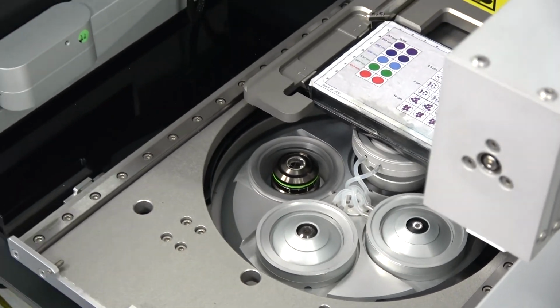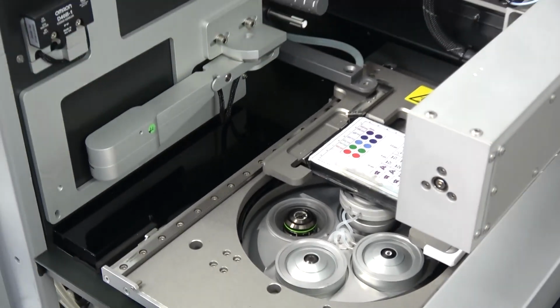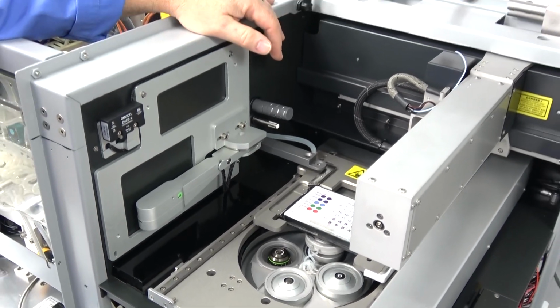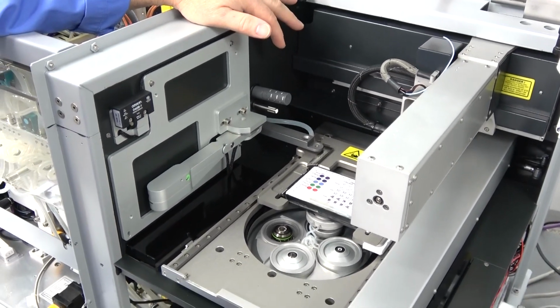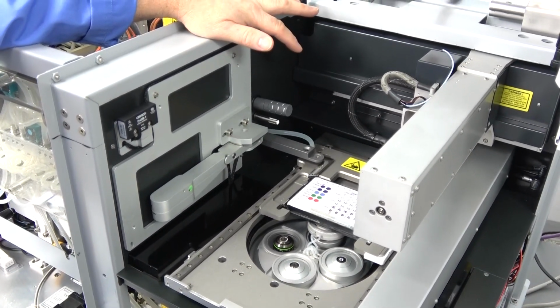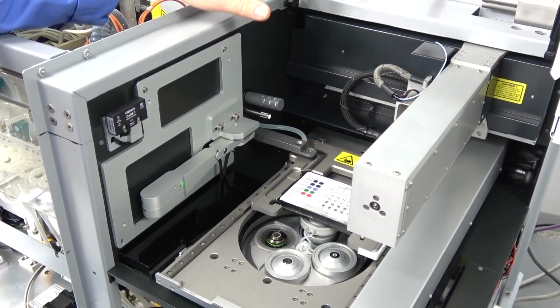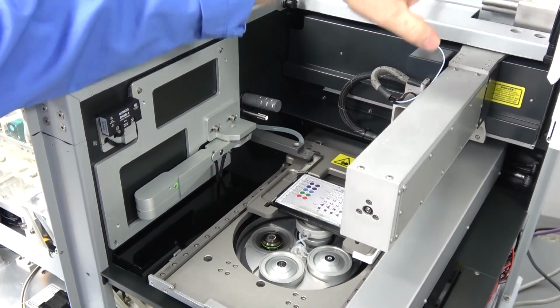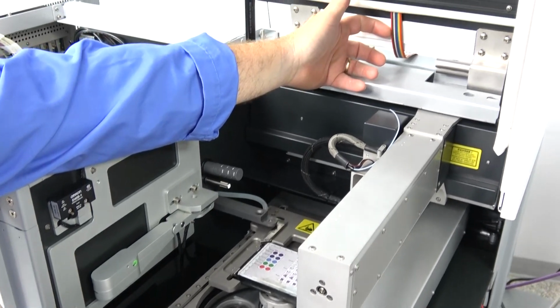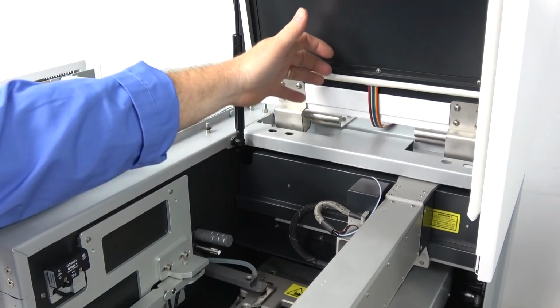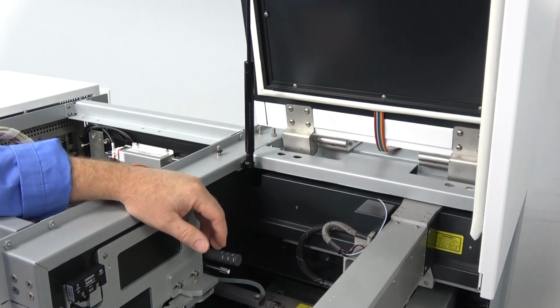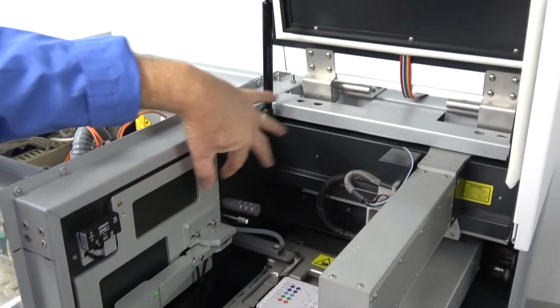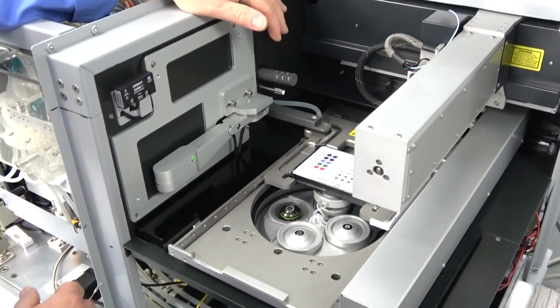In here, this is again a special chamber because it is for live cell imaging. What they do is embed all kinds of heaters and sensors built into the chamber, including the lid up here — you can see all the wiring coming in. So they're monitoring the temperature in every area, and on the sides, on the bottom, everything is being monitored.